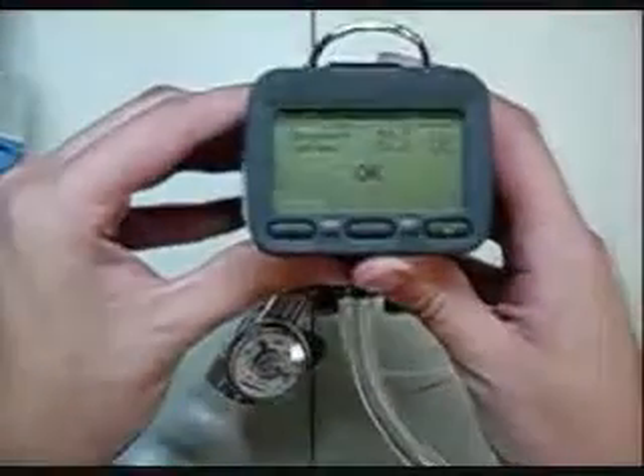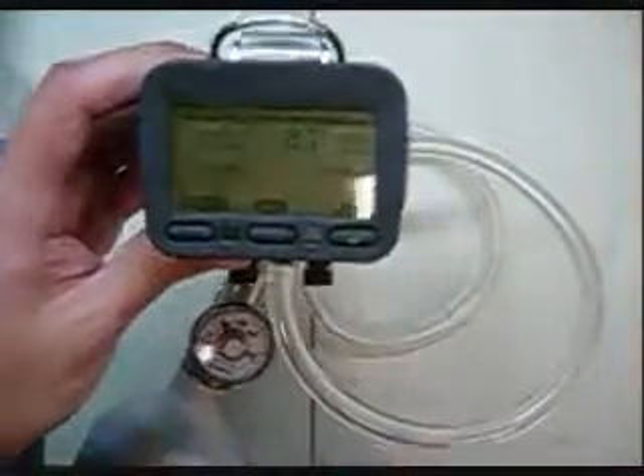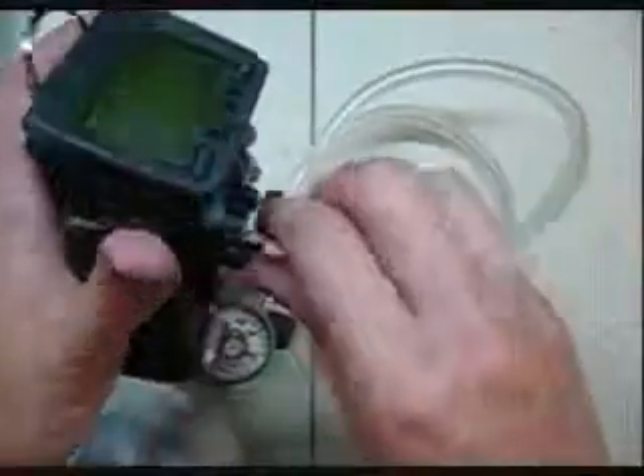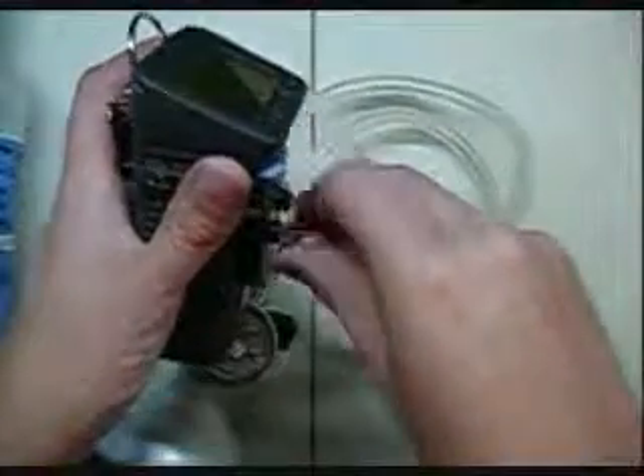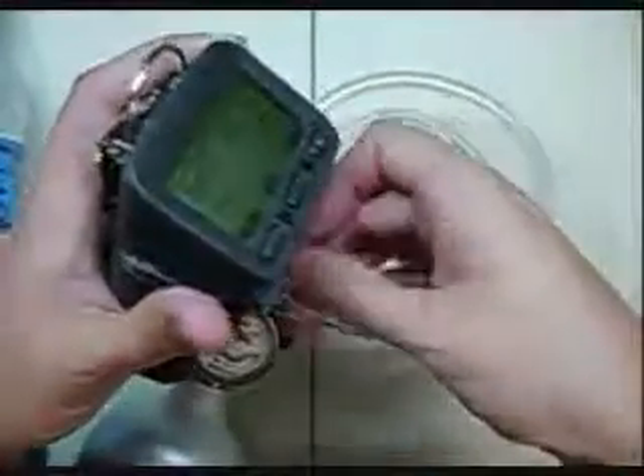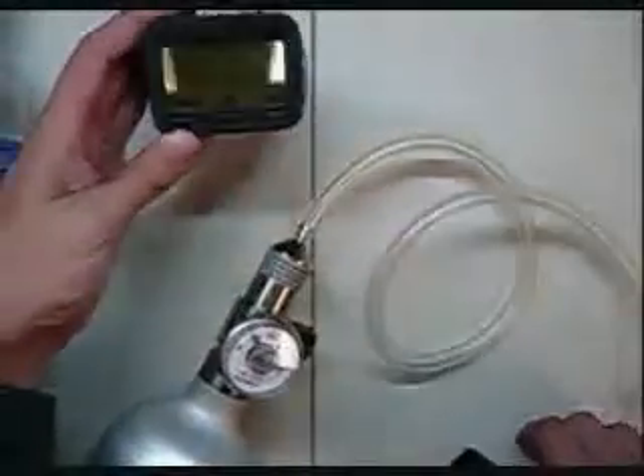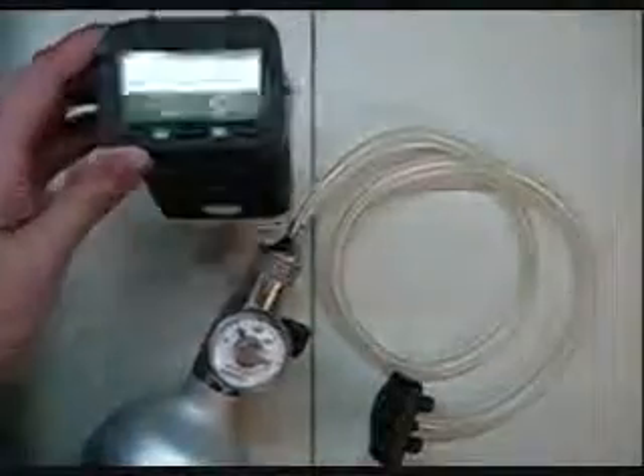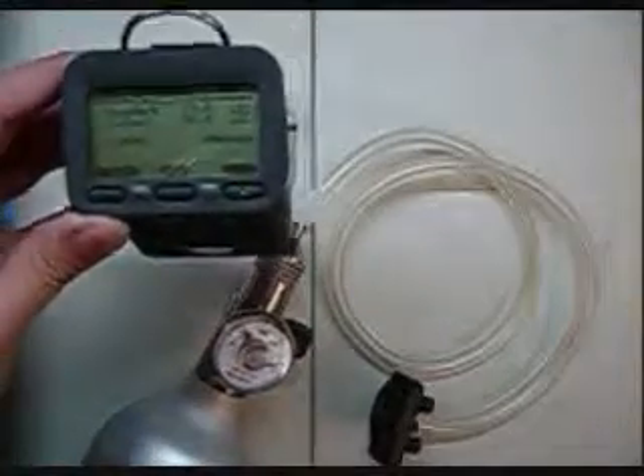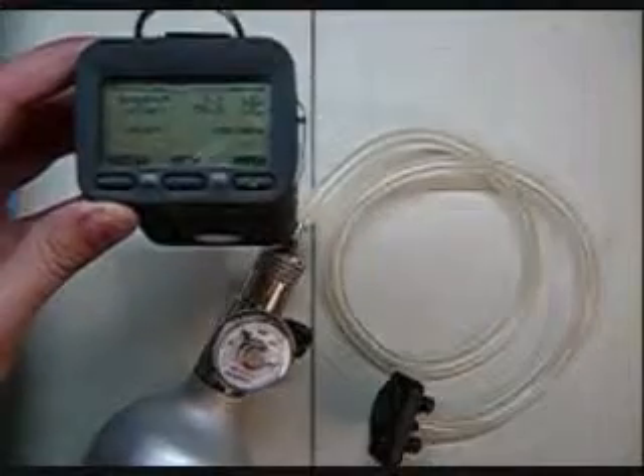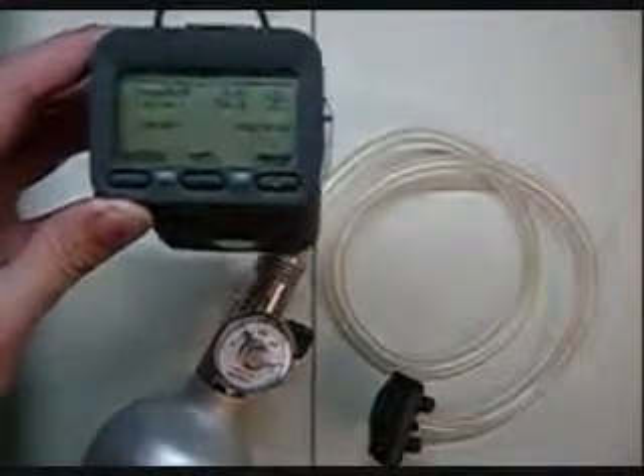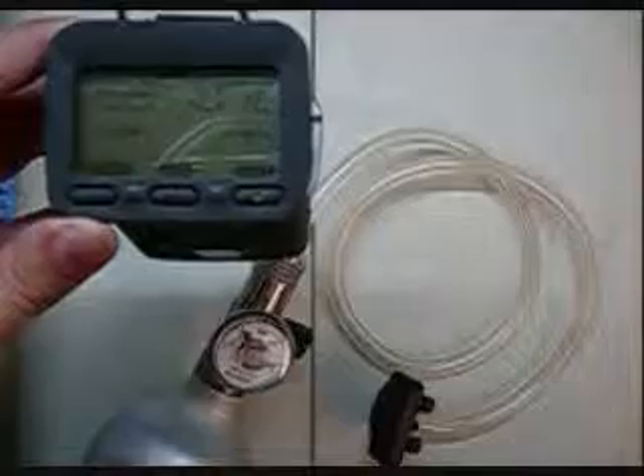Now you'll see it comes up and says OK. It's good news. Now it heads back to this readout screen. Go ahead, turn the gas off. Make sure that the readout reads real close to the cal gas value. Turn your gas off, and you can unscrew this cap. Now this is the point at which I would let it sit for a few minutes until it goes back down. We want to make sure this one goes back down to 0. It usually takes about a minute or so. Sometimes the ammonia and the SO2 might take a little bit longer for the reaction time.